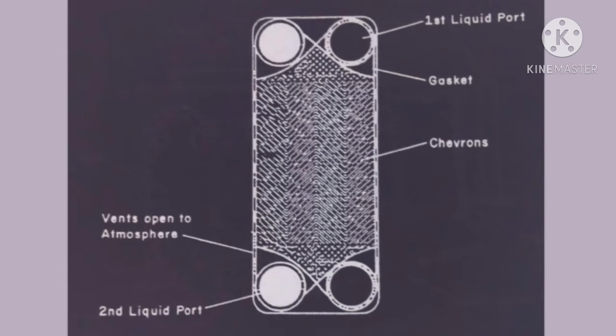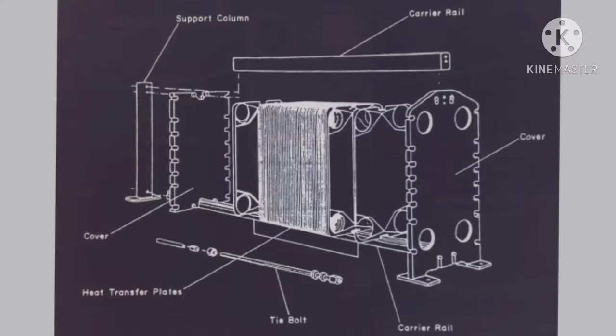The most important point is capacity can be increased by introducing plates in pairs. We can increase or decrease the capacity of the heat exchanger by introducing or excluding number of plates in pairs. If we want heat transfer efficiency to increase, we can introduce more number of plates in pairs. This is the biggest advantage of the plate type heat exchanger.